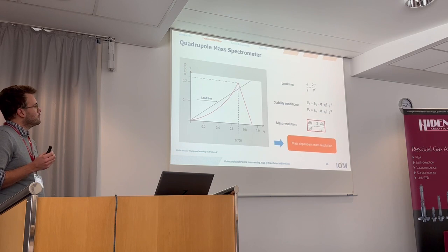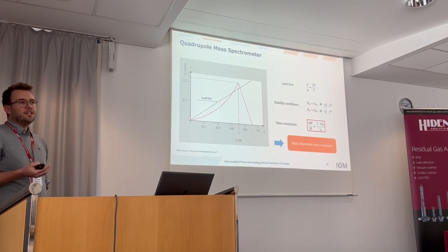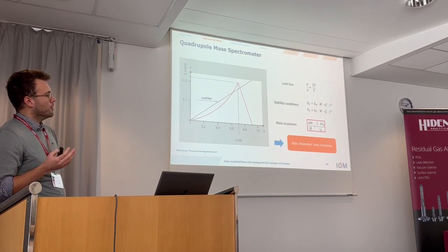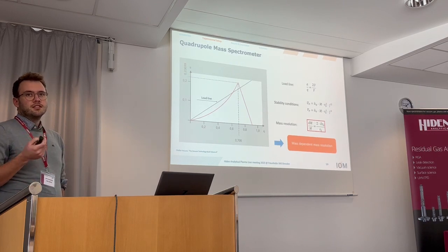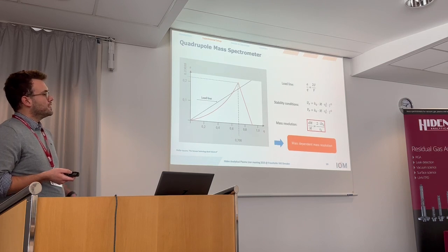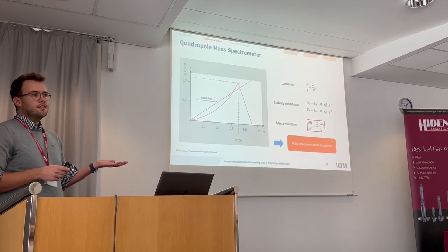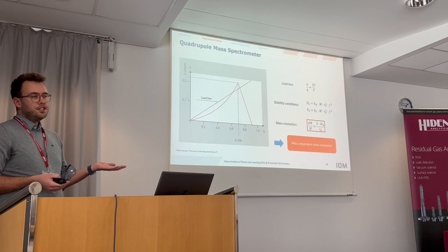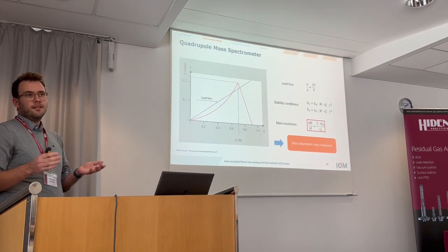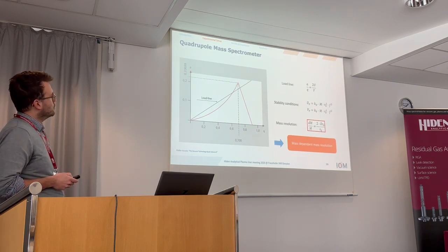And what I want to focus on most, when it comes to determining the composition of our ion beam, is the biggest challenge, as Carsten already mentioned: the mass-dependent transmission function. On one hand, we have different angular acceptance angles for ion energies, but since we are operating in an energy range over 100 electron volts, this is almost constant. So the biggest problem is the mass-dependent transmission function.